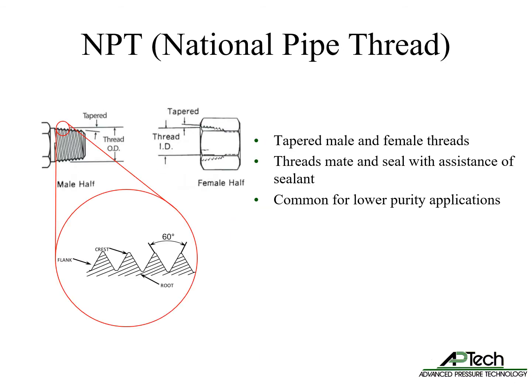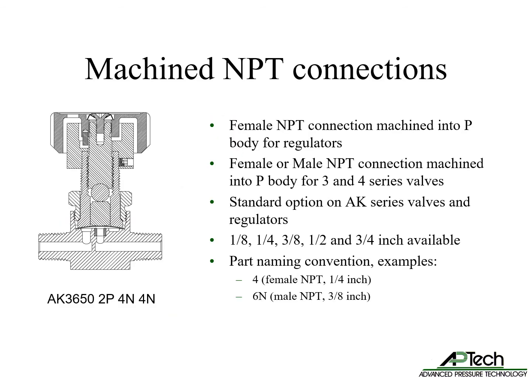NPT connections, or National Pipe Taper, feature tapered male and female threads. The threads mate and seal with the assistance of a sealant. NPT connections are very common for lower purity applications. The most common configuration for NPT connections are machined threads — either female for regulators, and female or male for 3 and 4 series valves.